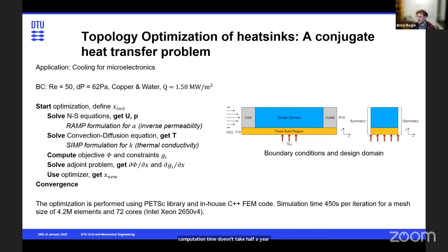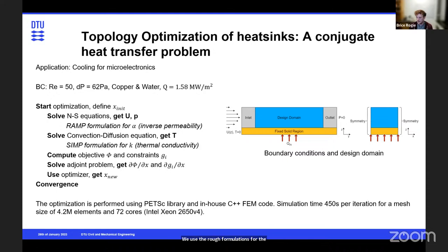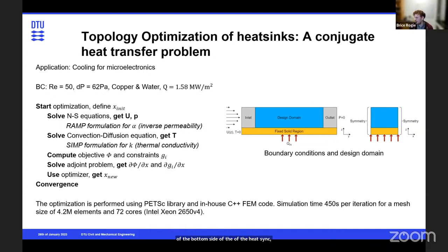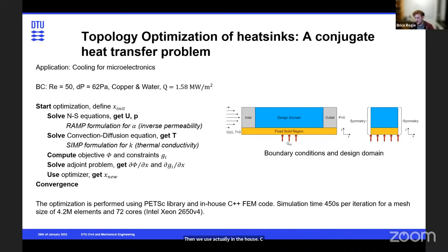The topology optimization is a classic conjugate heat transfer problem with one-way coupling of Navier-Stokes equations and a convection-diffusion equation. We use the RAMP formulation for the inverse permeability alpha and the SIMP formulation for thermal conductivity. The objective is to minimize the temperature of the bottom side of the heat sink where the heat flux is applied, with constraints on pressure drop and volume. We use an in-house C++ FEM code with the PETSc library. Simulation time is around eight minutes per iteration with a 4.2 million element mesh using 72 cores.